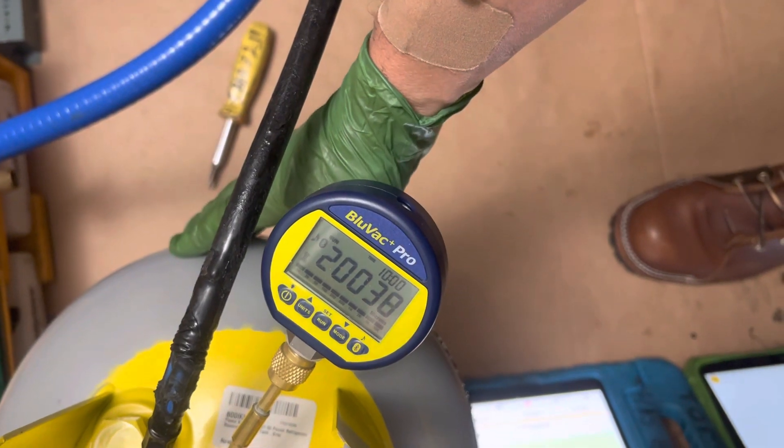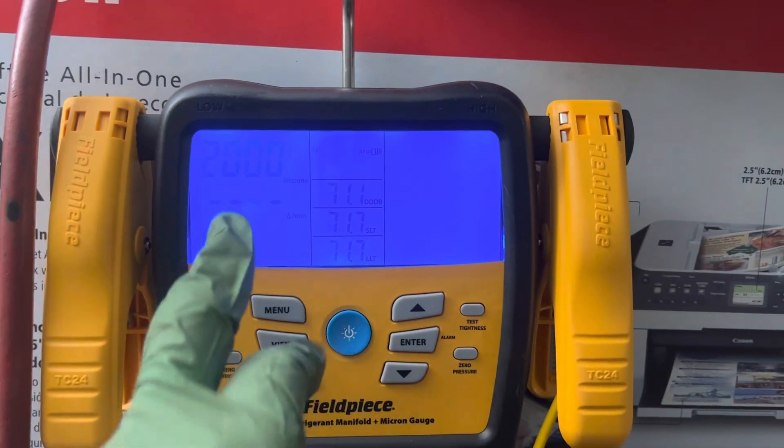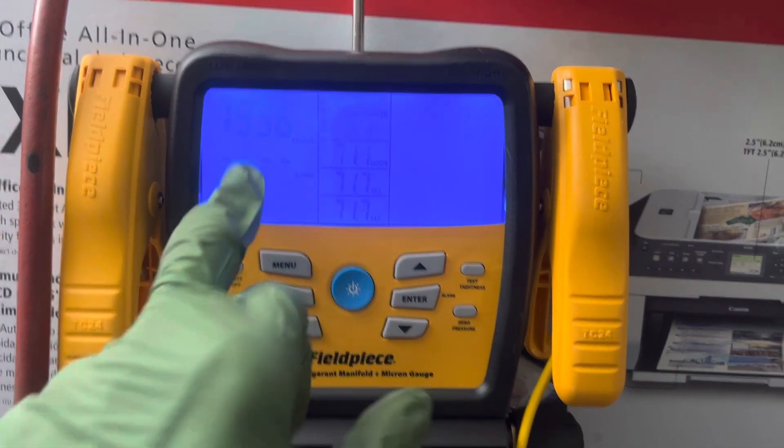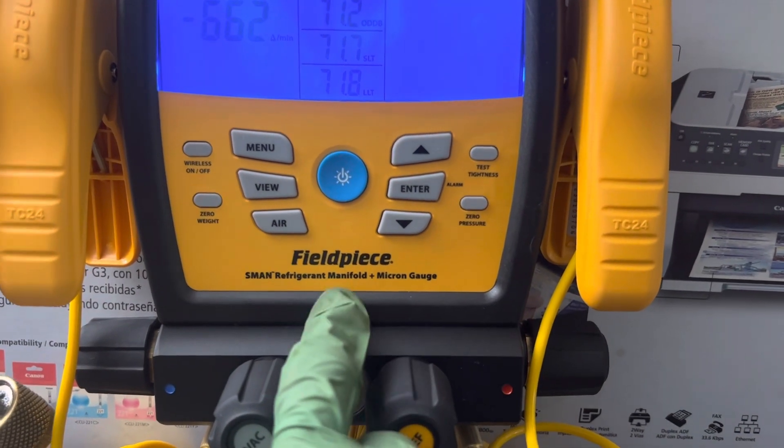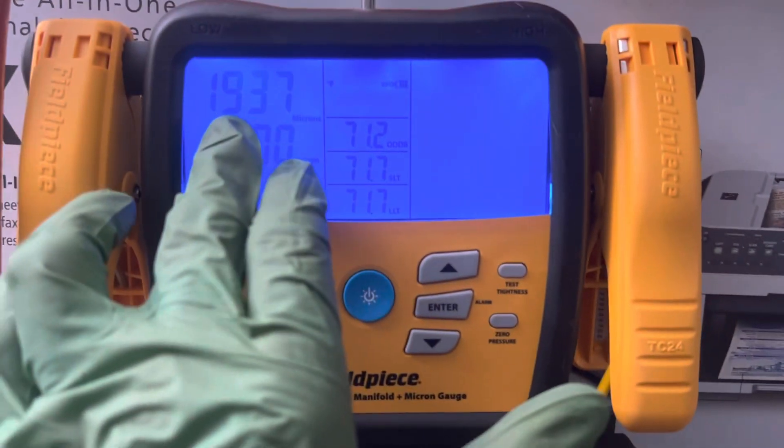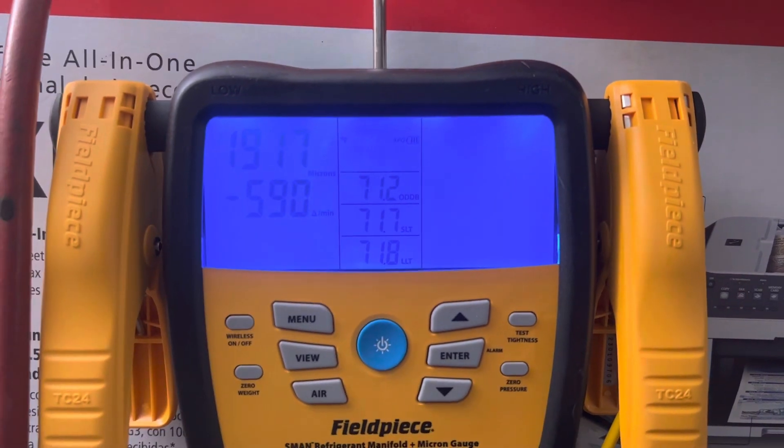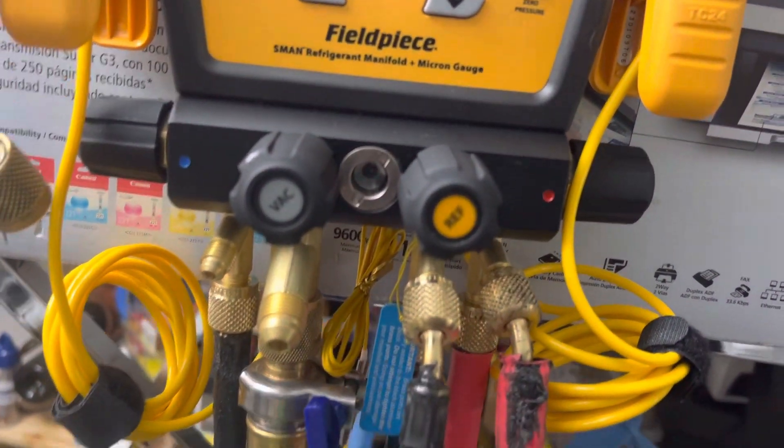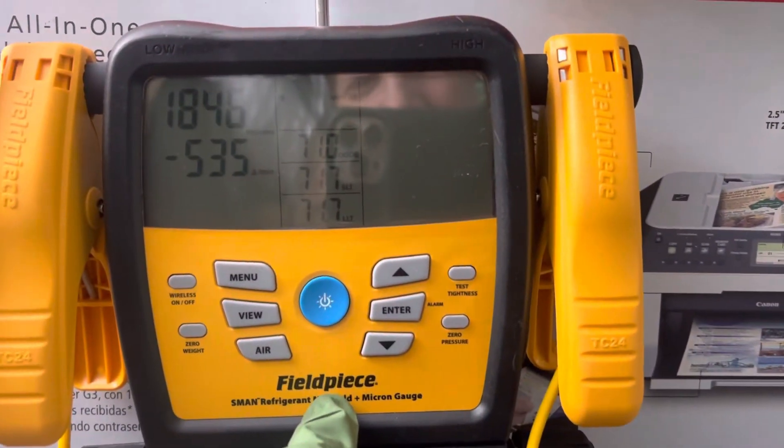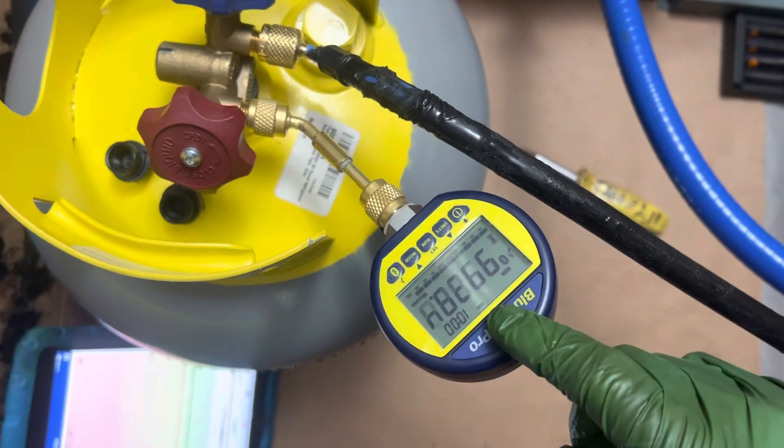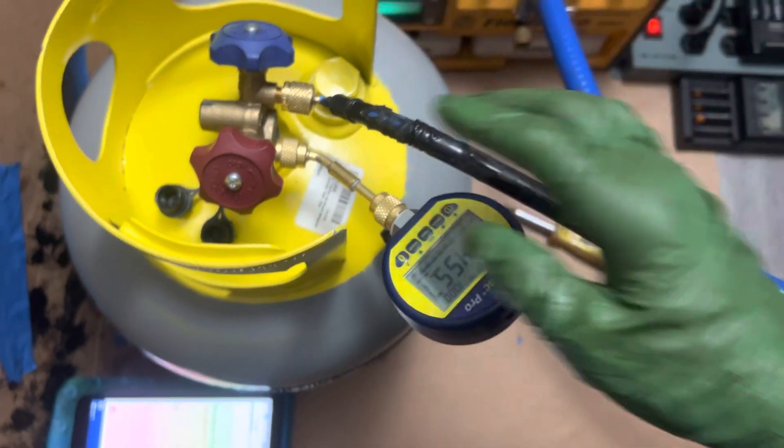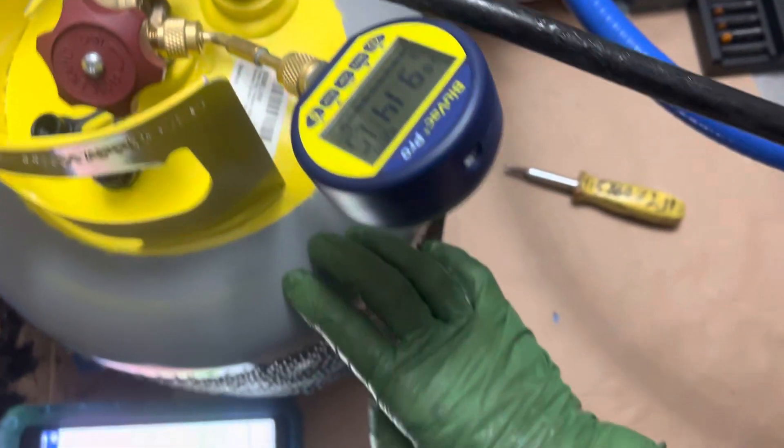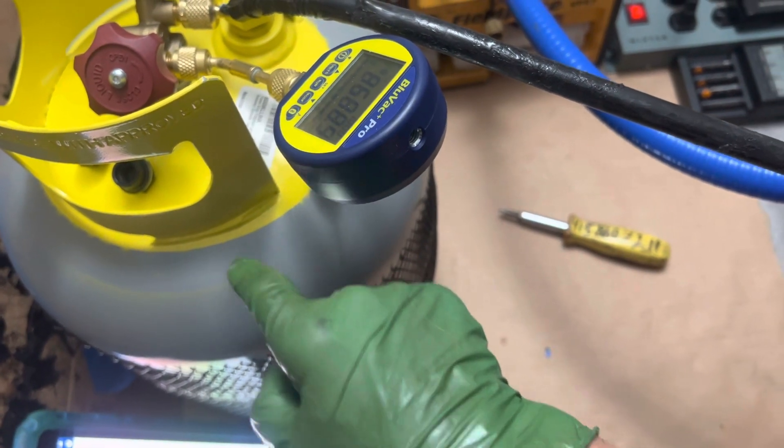Our container is now in the 20,000 micron region, and our micron sensor located inside the FieldPiece just got below the 2,000 micron region. You see the big difference? The micron reading right here is right next to where the vacuum is being pulled, so it's a completely different reading here than it is here. We're in the 10,000 region right now—that is the vacuum of the tank. So there's a big difference between the vacuum in the system compared to the vacuum in the hose.